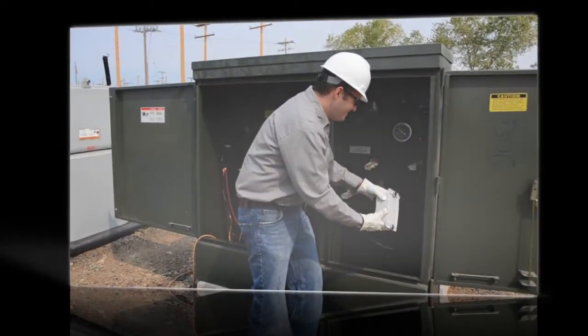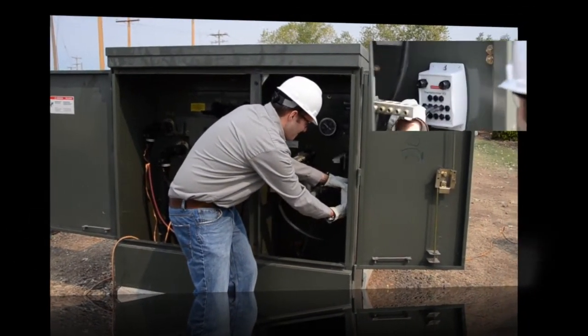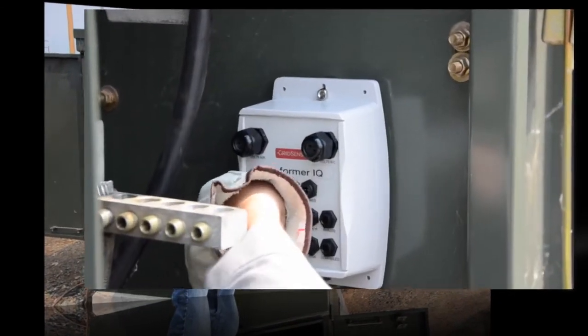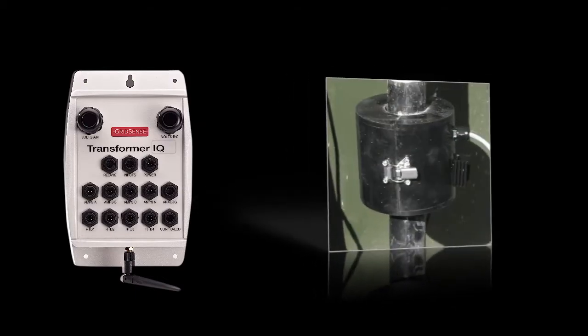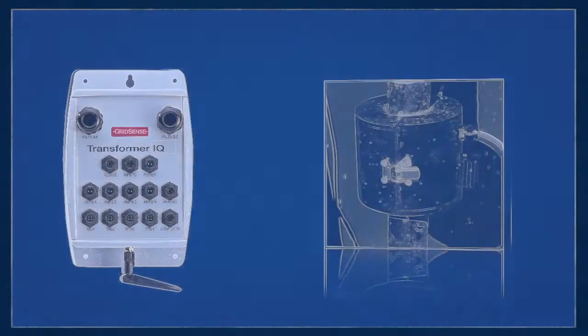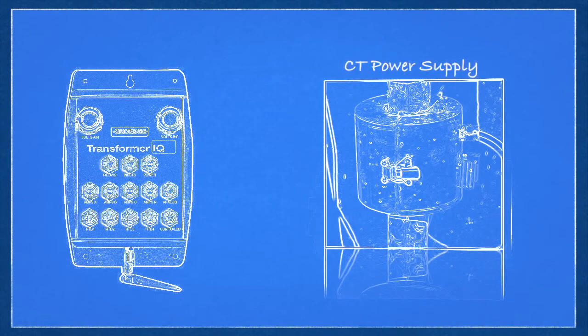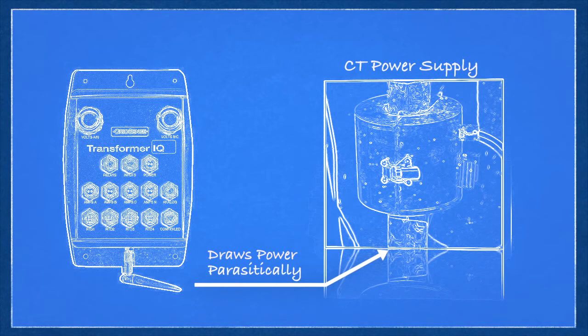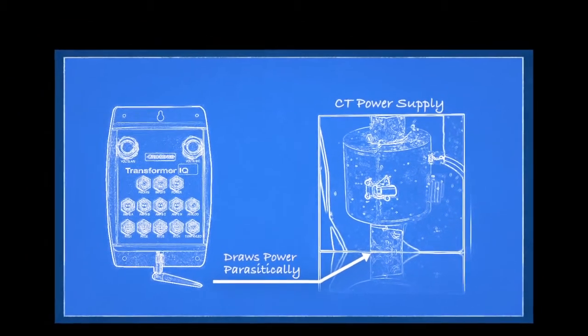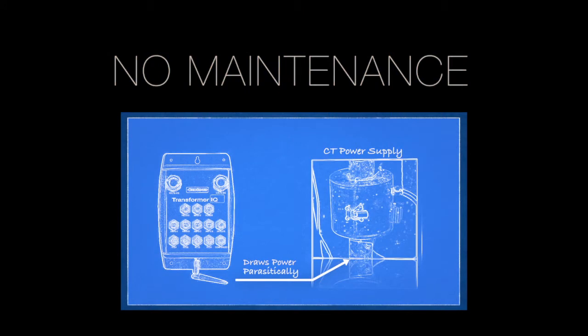What you're seeing is the installation of a new kind of monitoring system for dead front transformers and other assets. This system pairs the Transformer IQ monitor with a current transformer or CT power supply. This CT power supply draws power parasitically from insulated cables. Unlike battery-powered monitors, there's no maintenance, and you always know there's a monitoring solution at work.